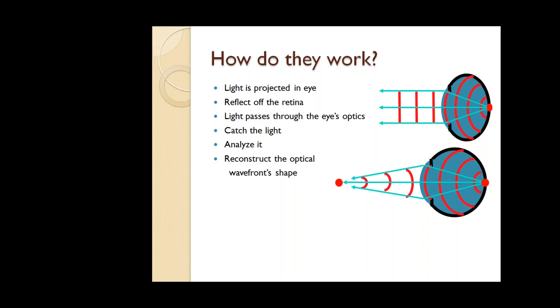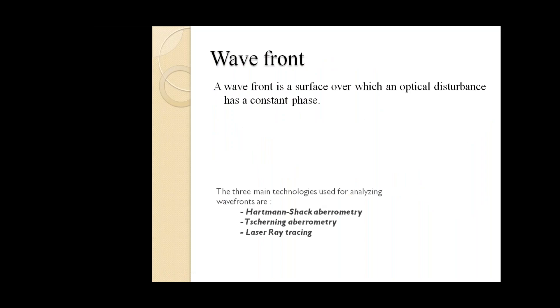The aberrometer works by projecting a light beam onto the cornea, which reflects off the retina. The light passes through the whole eye optics, is captured, analyzed, and the optical wavefront shape is reconstructed. The CCD sensor incorporated in the aberrometer analyzes each and every spot of the aberration and produces a report. The spherical plane wavefronts and spherical wavefronts are shown hitting the retina and returning to reconstruct the optical wavefront shape, with each spot recorded by the sensor.